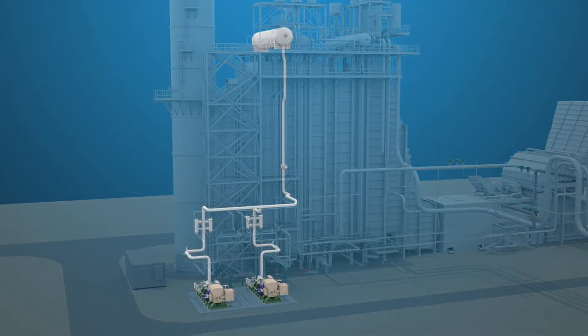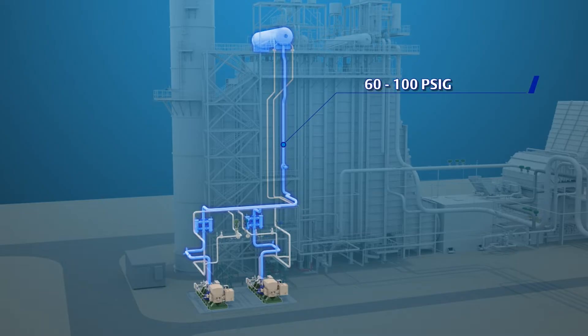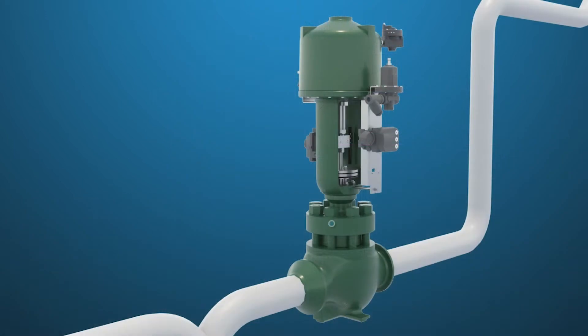Feed pump suction pressure is 60 to 100 PSIG. Pump discharge pressures range from 2,000 to 3,500 PSIG and recirculates back to the low pressure drum. The recirculation valve will see cavitating pressure drop for its entire operating range.